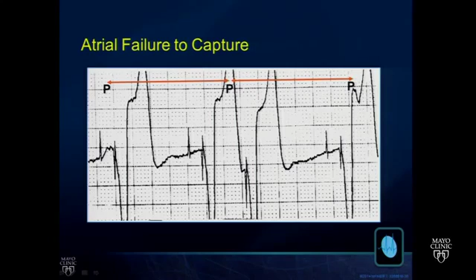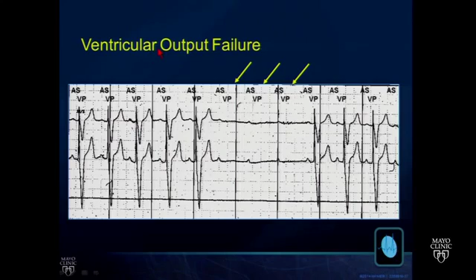Here's ventricular failure of output, not failure of capture, failure of output. In the early part of the recording, we see a good ventricular spike, so it's not isoelectric, and then it disappears and resumes again. And we have the luxury of the marker channel that tells us that the device thinks it's closing the circuit, VP, for ventricular pacing. So this is an interruption of the circuit that is preventing energy from being applied to the myocardium. This is ventricular failure of output.